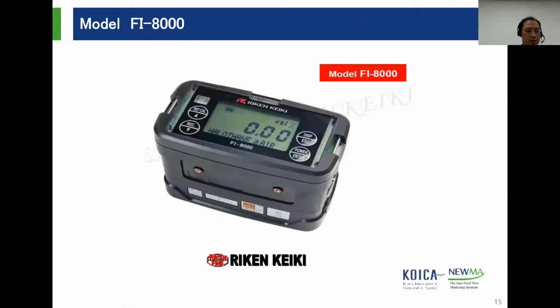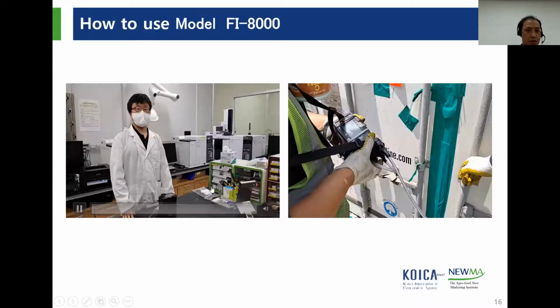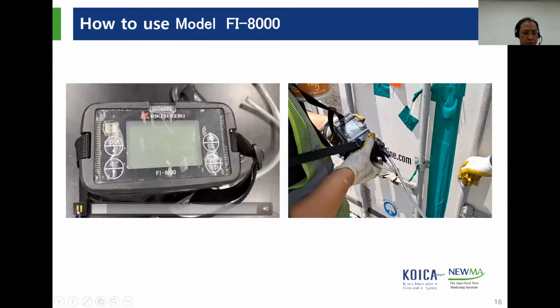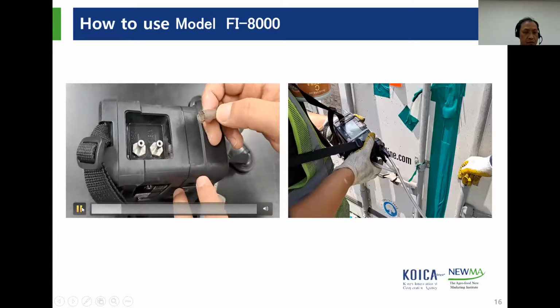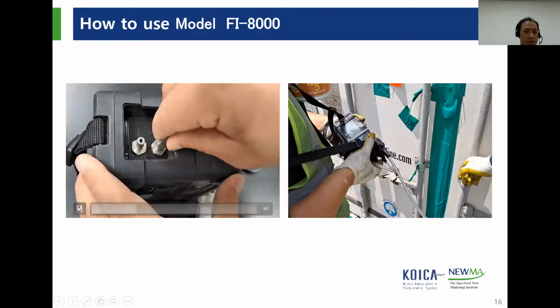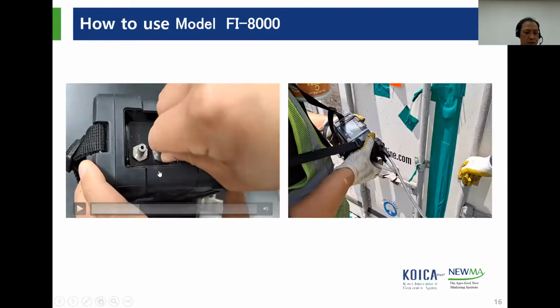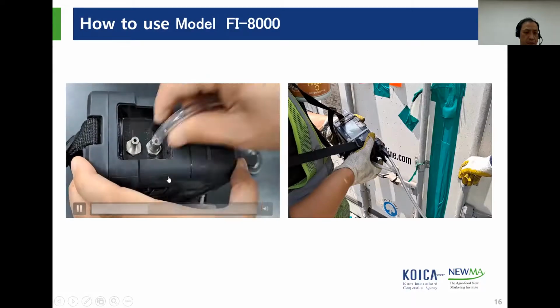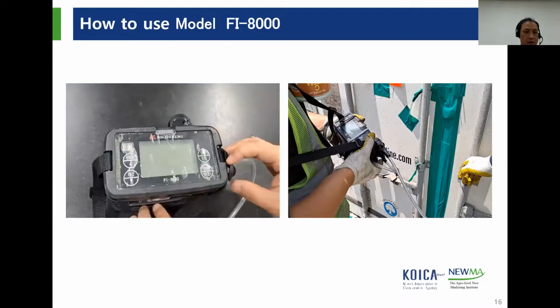This is model FI 8000, the successor model of FI 21. It is lighter than the FI21, and the four corners of the detector are curved to alleviate the impact when dropped, and a rubber pad is attached to the lower part. How to use the FI 8000 is simpler than the FI 21. After connecting the absorbers of calcium chloride and soda lime to the gas inlet, press the power button.